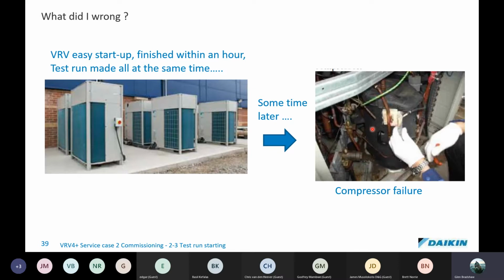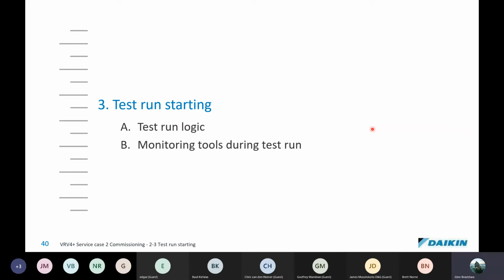If you've been pushed into a rush and you try to do this, it's very easy, and I've seen this happen not just with VRV systems. It has happened on sites with multiple splits where piping was swapped around and the guy turned everything on together and tried to commission it like that. Lo and behold, a few weeks or months later there are dead compressors and everybody's saying this product's soft. It actually turns out the piping was swapped around, and so it causes compressor failures. So what happens in the test run? You often ask us about the logic, so let's go through it and have a look.